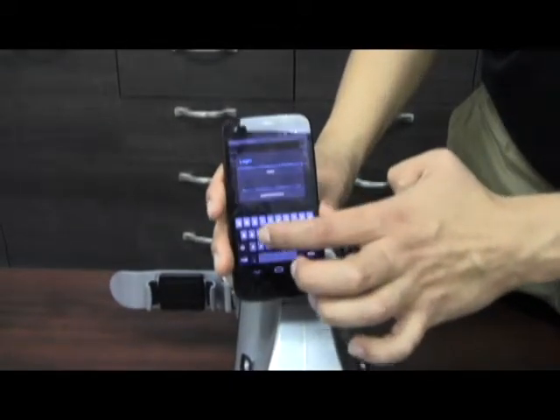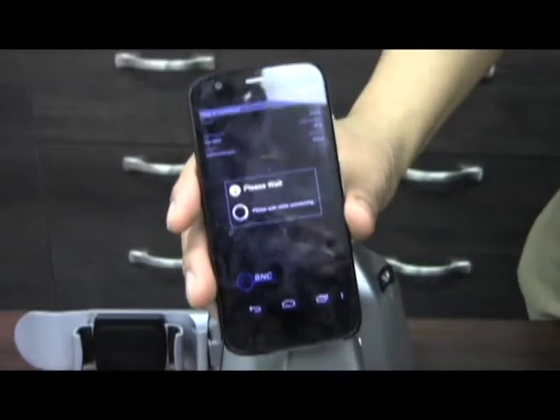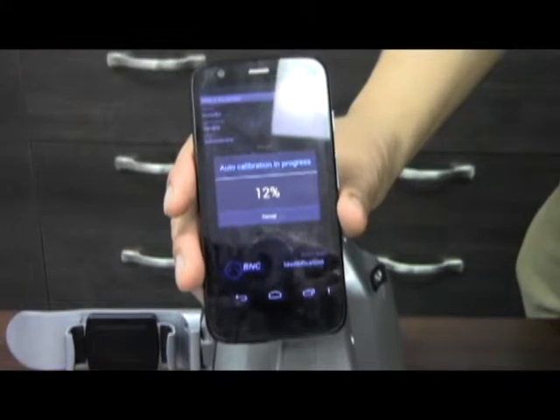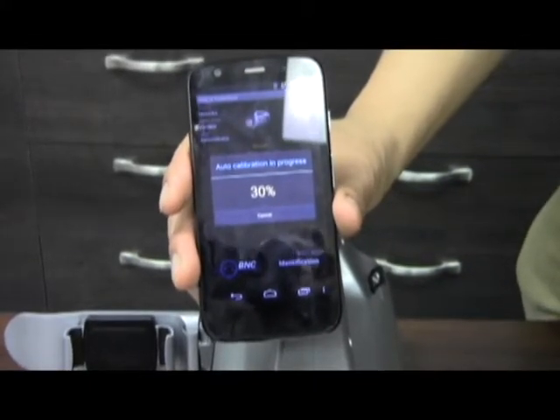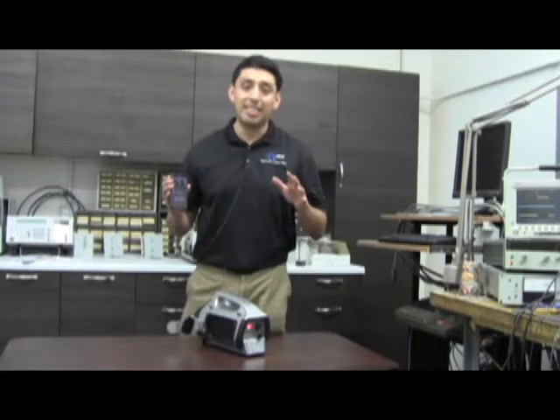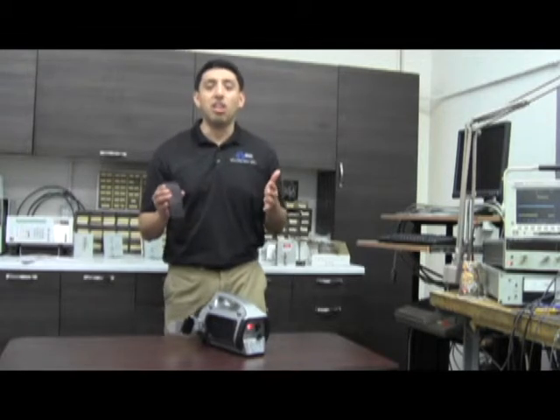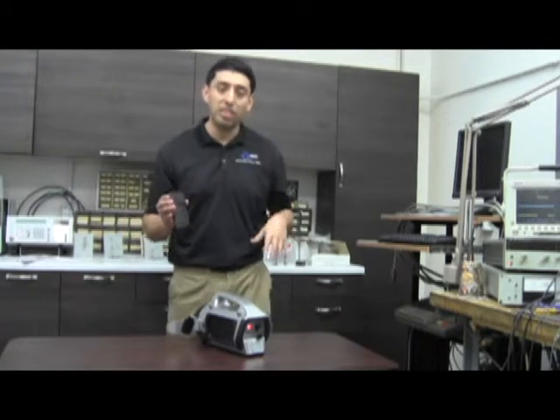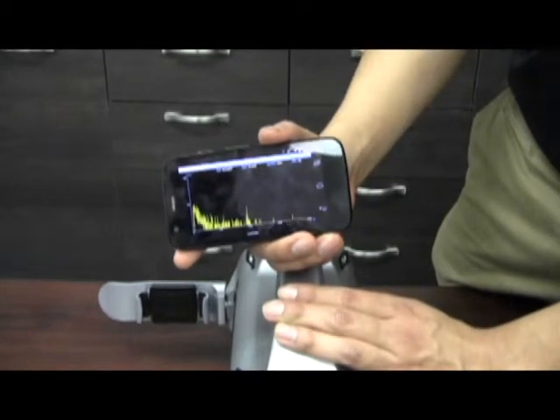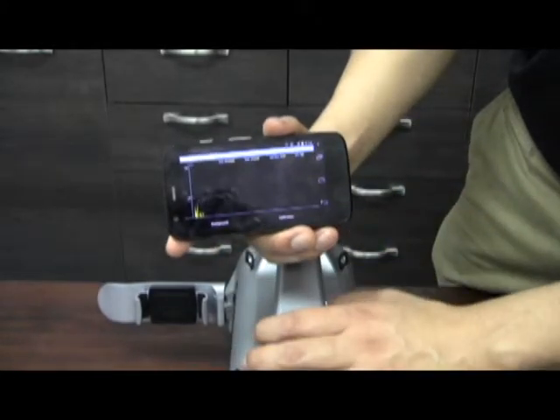You'll be led to a menu that gives you access either to user or administrator. The standard password will be 1234. After that, you'll see the auto calibration in progress — that takes around 10 to 15 seconds while it gets an understanding of the environment and checks if the spectrum is off. If successful, you'll see 'auto calibration success'; if the spectrum is off, it will show failure and you'll need to go through manual calibration with a Cs-137 source. Once calibrated, you get your dose rate, counts per second, and turning 90 degrees you get your high definition linear spectrum — something that was definitely not possible with our old 945 and QCC.